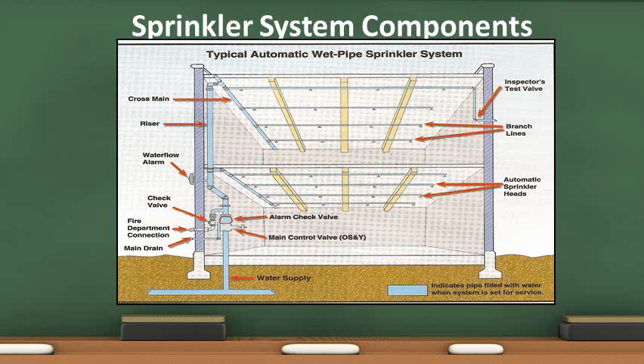The water then travels to the alarm check valve or flow switch. The flow switch is not shown in the diagram. The alarm check valve and flow switch sound a local alarm indicating water is flowing through the system. The riser carries the water up into the cross main. The cross main carries the water to the branch lines, which carries water to the sprinkler heads. The main drain releases water from the system for maintenance purposes. The inspector's test valve is located at the most remote portion of the sprinkler system and allows a qualified inspector to conduct tests to ensure the water flow alarm activates within 45 to 90 seconds.